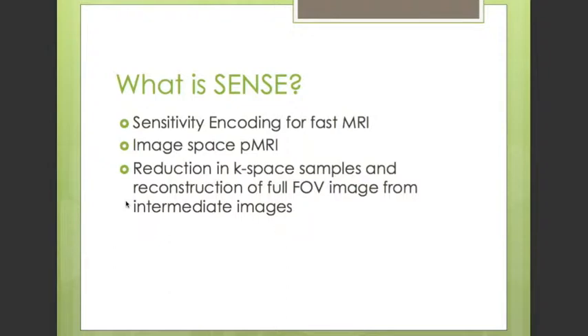The algorithm benefits from the difference in sensitivity of each coil used in imaging. The sensitivity encoding of the coils is stored in an array, and this array, when conducting 2D Fourier imaging with Cartesian k-space sampling, reduces the number of Fourier encoding steps needed. The technique reduces scan time by increasing the distance between k-space sampling positions while maintaining the maximum k-values and approximately preserving spatial resolution. The ratio of the reduced k-space samples to the original number of samples is referred to as the reduction factor.